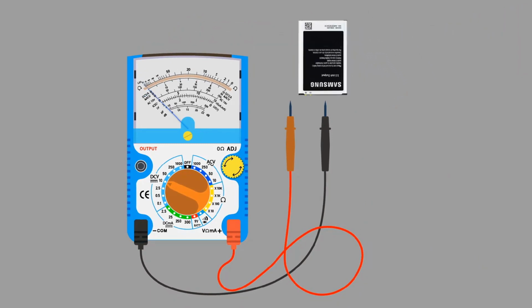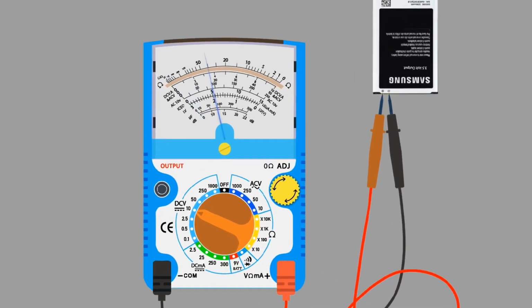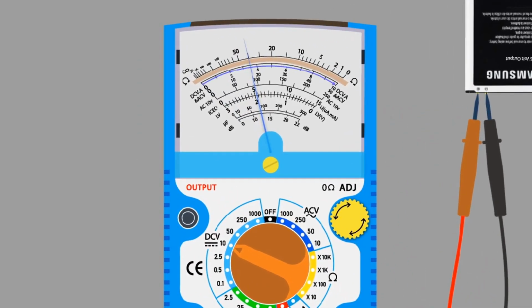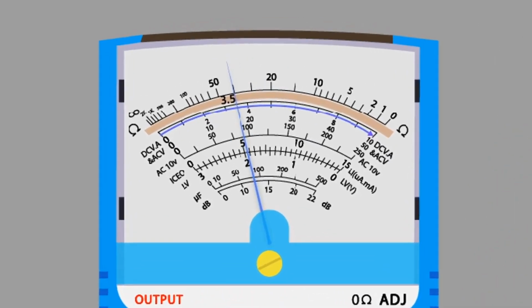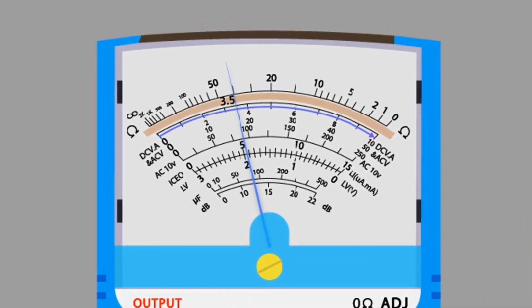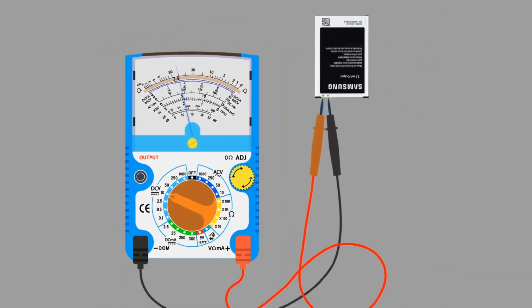Now we'll connect the probes directly across the terminals of the battery, and as we could see, we have a deflection. We'll take the readings on the 0 to 10 scale. If we had selected 50, we would have taken the readings on the 0 to 50 scale, and similarly, if we had selected 250, we would have taken readings on the 0 to 250 scale. As you can see, the value is almost 3.5, between 3.5 and 4. So we can see that this voltmeter is giving the correct value.